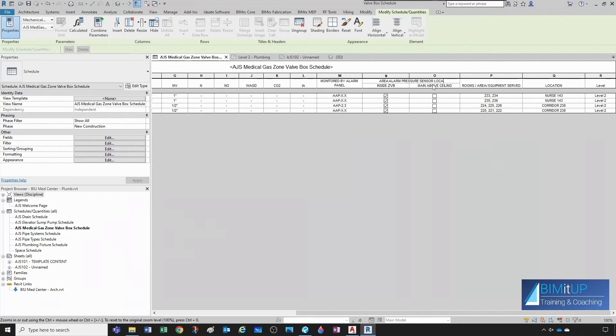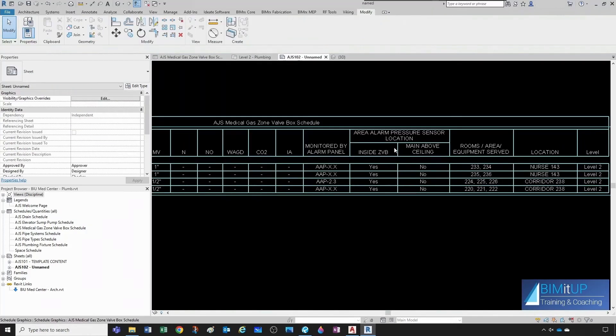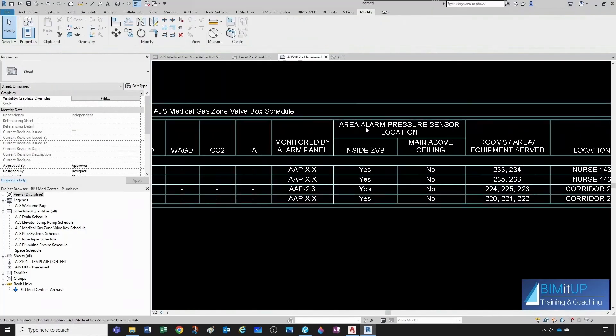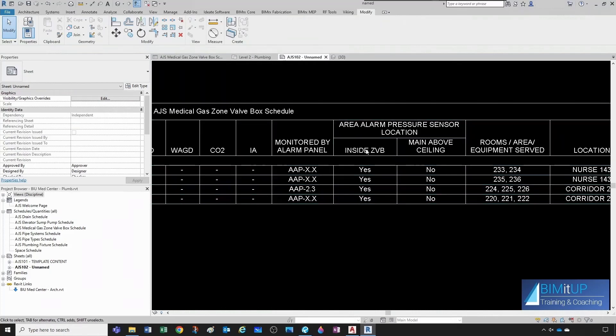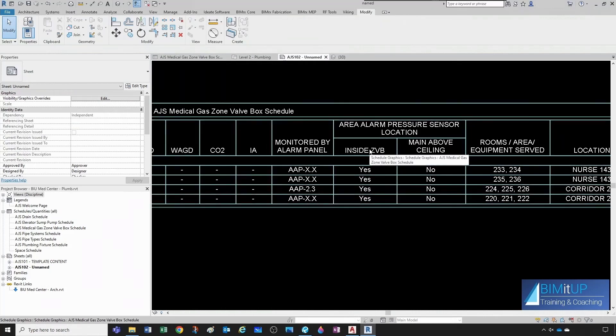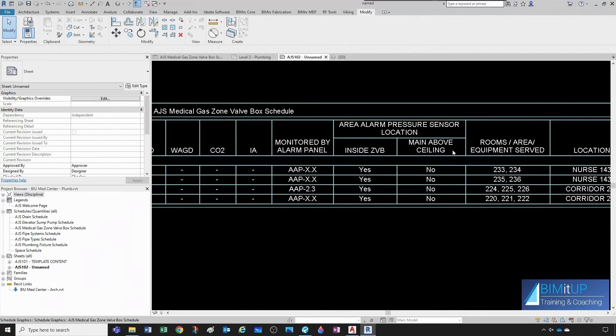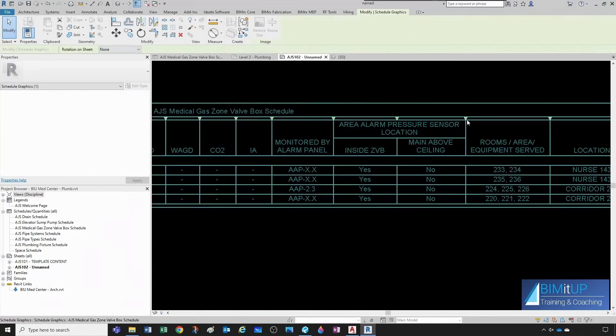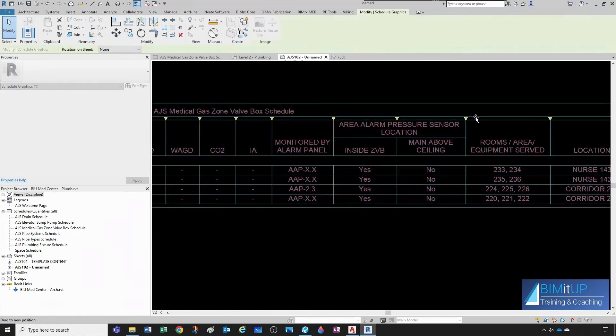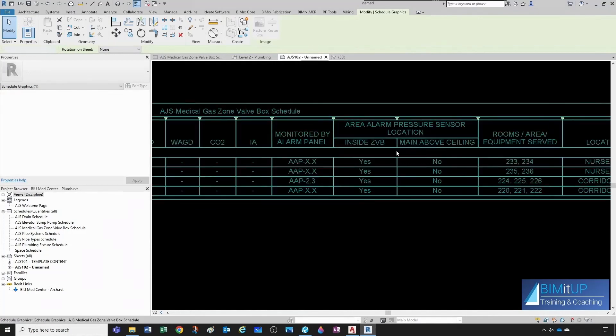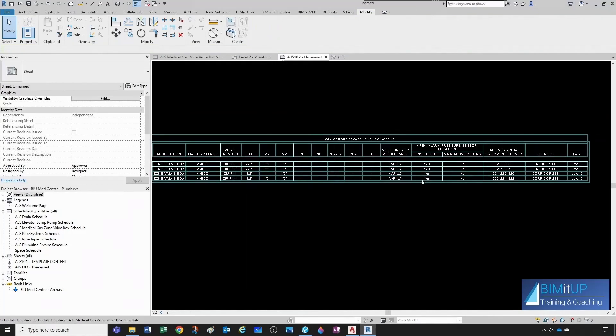location. So, now, when we come here, area, alarm, pressure, sensor, location, inside zone valve box, or on the main above ceiling. Actually, I think it would be nicer if we have that like that. And there you have it. That's how you create your zone valve box schedule.